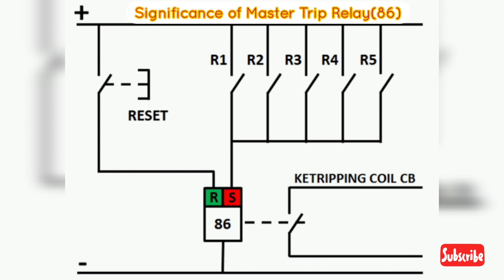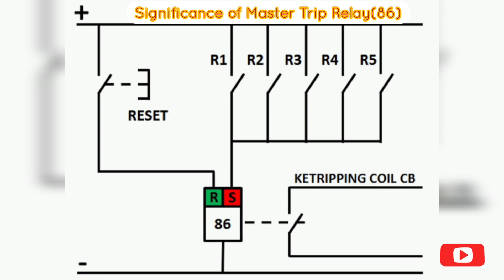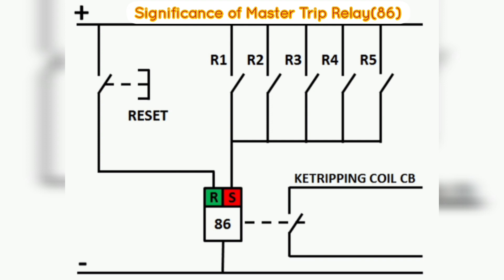Next we learn about the significance of Master Trip Relay 86. First, the Master Trip Relay receives signals from protection relays and outputs a tripping command to the trip coil of a circuit breaker, thus providing isolation between the protection relays and the circuit breaker's trip coil. If we directly wire protection relays to the trip coil and a fault occurs in the trip coil, it may cause burning of the protection relay contact. Since protection relays are expensive, direct interfacing with the trip coil is not advisable. A Master Trip Relay is therefore used to provide isolation.